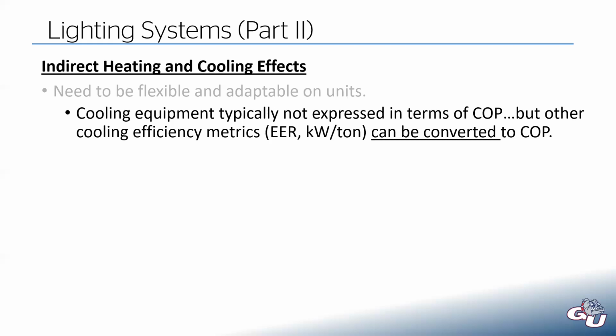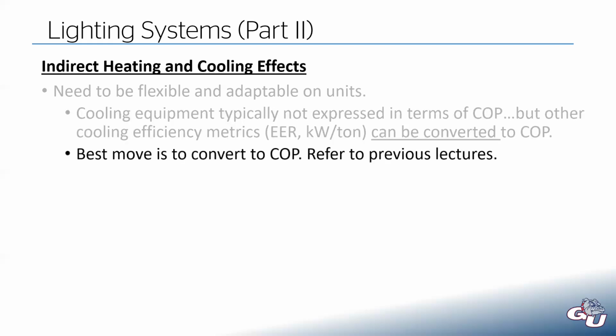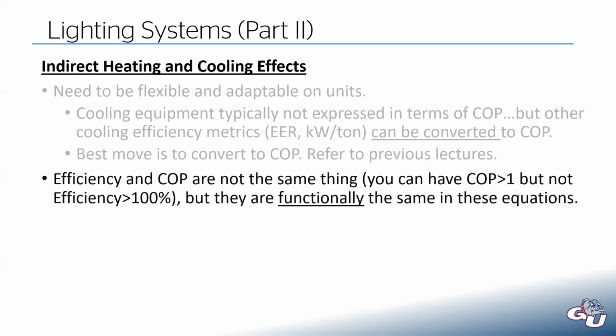They're typically going to give you something like EER or kW per ton, but those metrics can be converted. So if it were me, I would convert those to COP. COP is the easiest metric to work with because it's unitless. So once you have it in COP, it just makes things a lot simpler. But efficiency and COP are not necessarily the same thing, because you can have a COP greater than 1. You cannot have an efficiency greater than 100%. But in terms of our equations, in terms of input and output and efficiency, COP and efficiency are functionally the same when you're doing these equations.